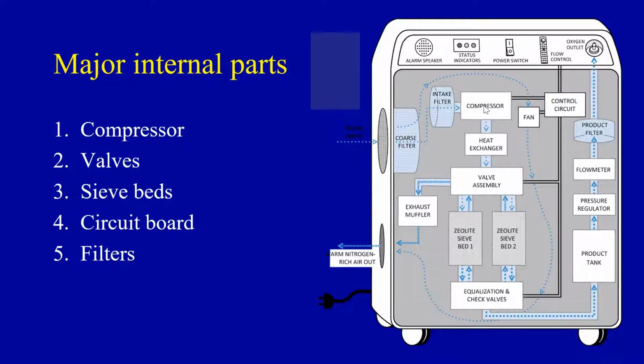Then it goes through a heat exchanger, which means a little bit of the moisture is removed from the air we breathe. And then it goes through some valves. The valves are quite important because they direct the flow of gas to one of the cylinders - I'll show you the cylinders - and then to the other cylinder. So one and then the other, moving backwards and forwards about every 5 seconds.